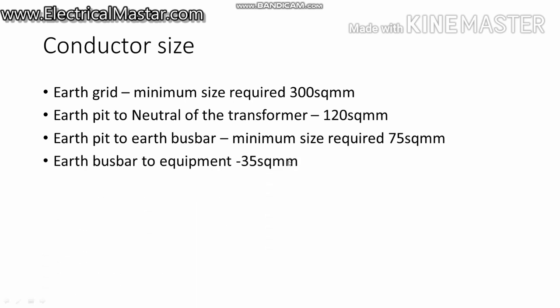And fourth is the earth bus bar to the equipment. From the earthing bus bar distribution to the individual equipment, you can use a minimum size of 35 square mm, depending on the equipment. 35 square mm is the minimum needed for a transformer, generator, or heavy load switchgear. For less load like DBs, like emergency DBs, you can use 10 square mm, which is also enough.